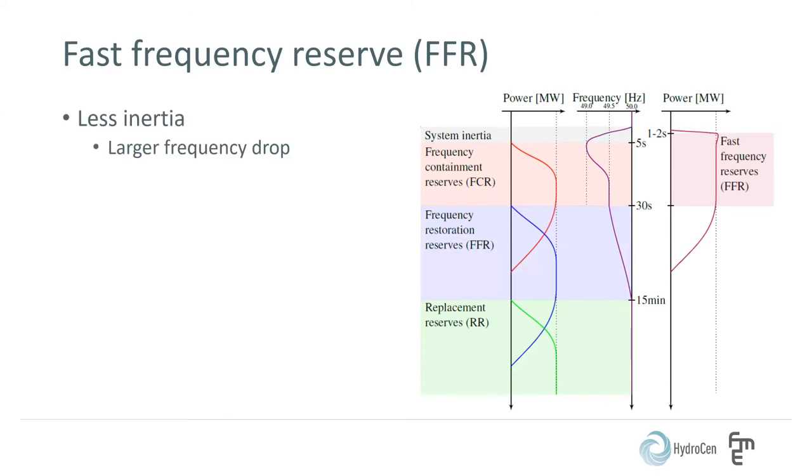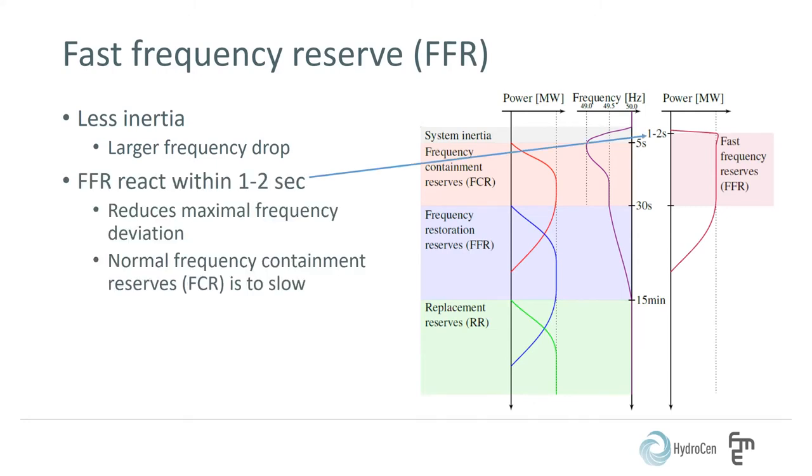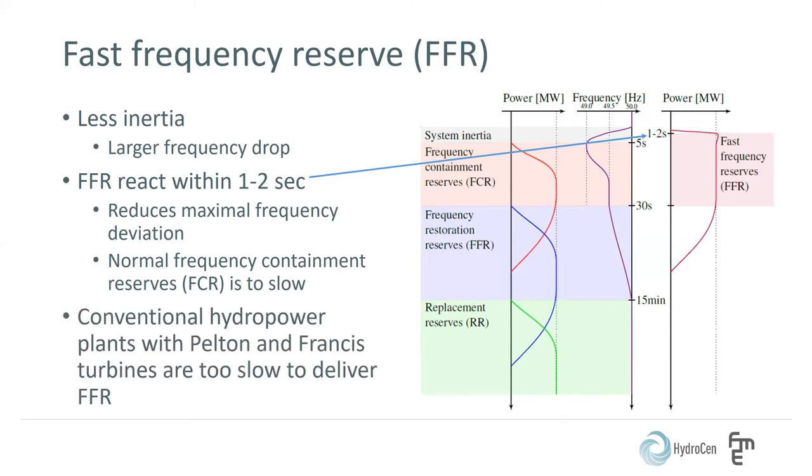As mentioned, the future grid with less inertia will experience larger frequency drops. Fast frequency reserves, FFR, are suggested as new auxiliary services. By reacting within one to two seconds, the FFR will reduce the maximum frequency deviation. In comparison, frequency containment reserves, FCR, are activated after the frequency has reached its maximum deviation approximately five seconds after the disturbance. And thereby, it is too slow. Also, the power response from conventional hydropower plants with pelton and Francis turbines are too slow to deliver FFR.